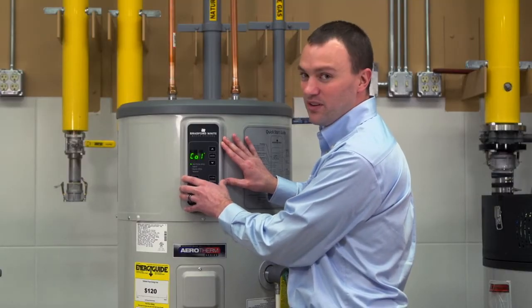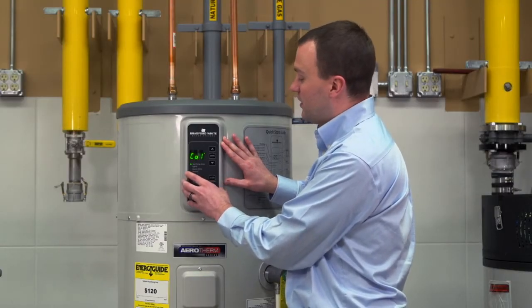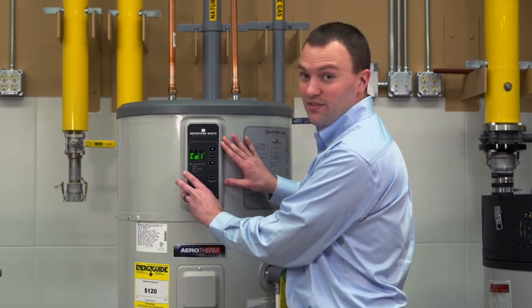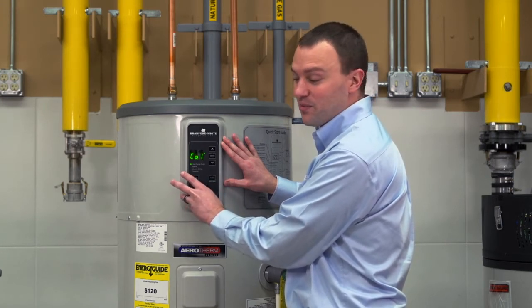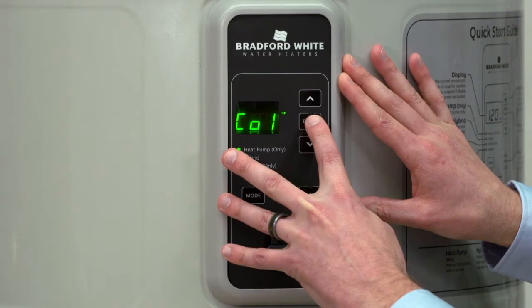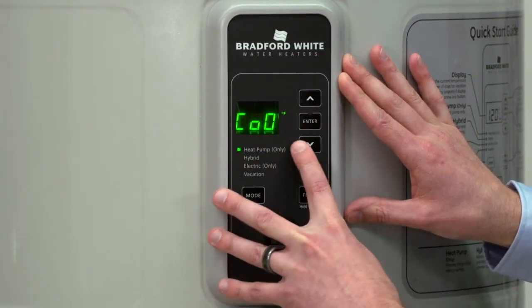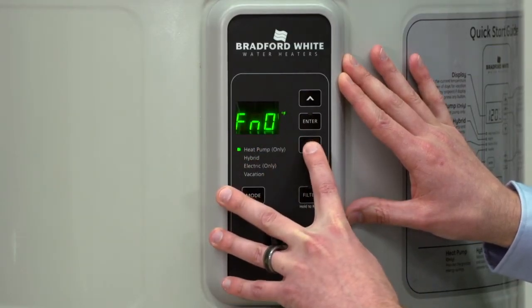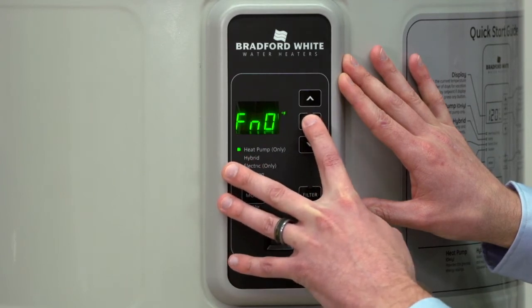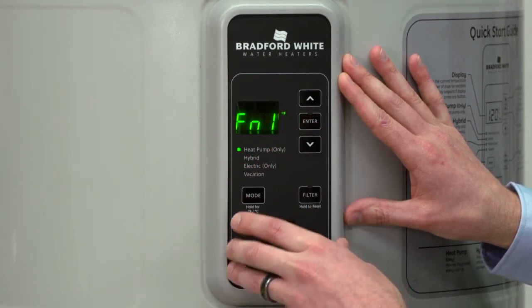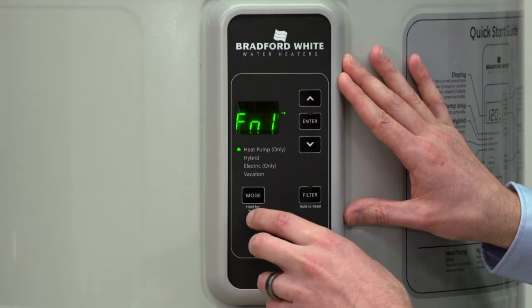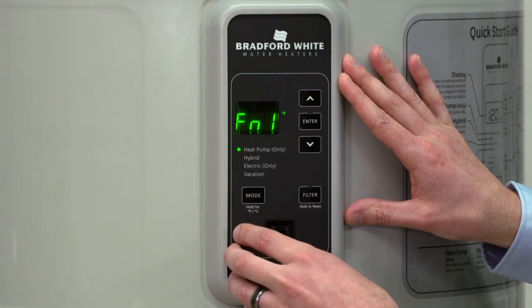You may hear some noise. You may hear the compressor. Nothing to worry about. Just verifying that we do have 240 volts to this component, so we do need to be careful. Go ahead and turn the compressor off. We'll now go down to the fan, and we'll go ahead and turn the fan on. Again, you should be able to hear the components come on, and then we'll be able to turn the component off.